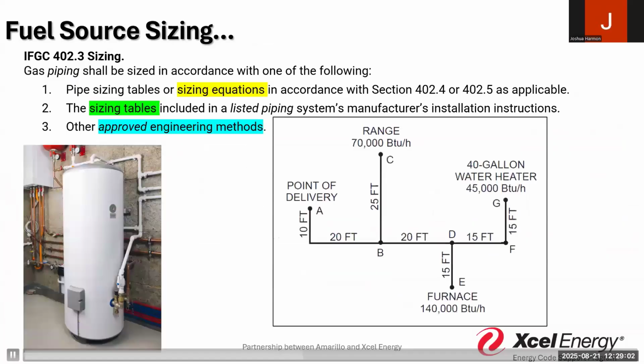If we look at a very basic home with a simple range, furnace, and water heater all operating off one gas line, we've sized that line historically, and even in today's design, to meet a specific gas load. We've loaded the components, figured out the right size piping based on length or some other engineering methodology, and got a regulator at the point of delivery sized to address our needs and pressures.